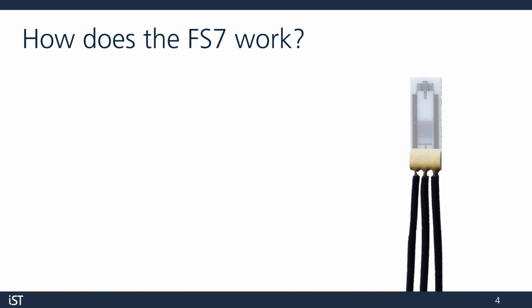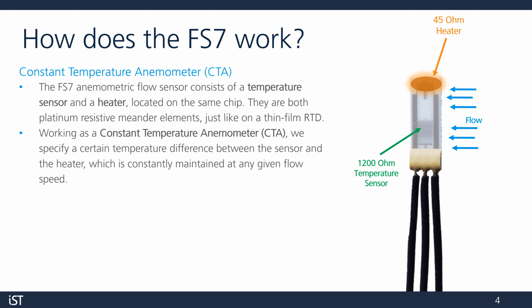Let's go a little more in depth and see how a gas flow sensor like the FS7 can measure air velocity. The sensor works as a constant temperature anemometer, or CTA for short. It consists of a temperature sensor and a heater located on a single chip. Both elements are platinum resistive meanders, just like what you'd find on a thin film RTD. We specify a certain temperature difference between the sensor and the heater. This difference should be constantly maintained at any given flow speed.